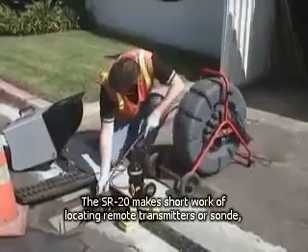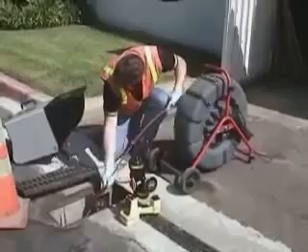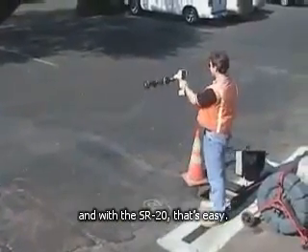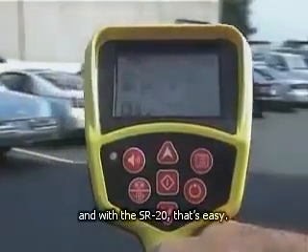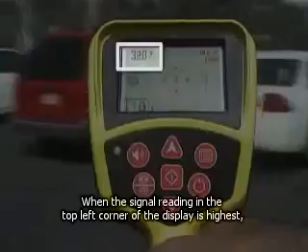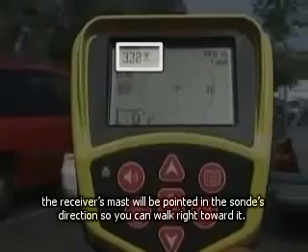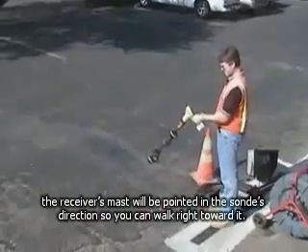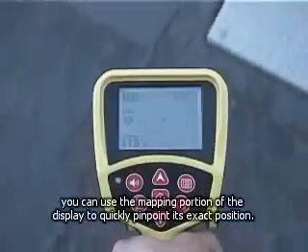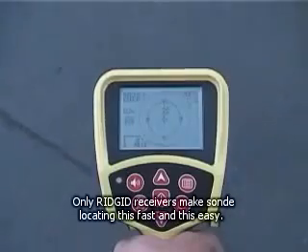The SR20 makes short work of locating remote transmitters, or sonde, like the one in this RIDGID SeeSnake video pipe inspection system. To locate a sonde, you have to know approximately where to begin looking for it, and with the SR20, that's easy. Simply extend the receiver and sweep it slowly in an arc. When the signal reading in the top left corner of the display is highest, the receiver's mast will be pointed in the sonde's direction, so you can walk right toward it. Once you get close, you can use the mapping portion of the display to quickly pinpoint its exact position. Only RIDGID receivers make sonde locating this fast and this easy.